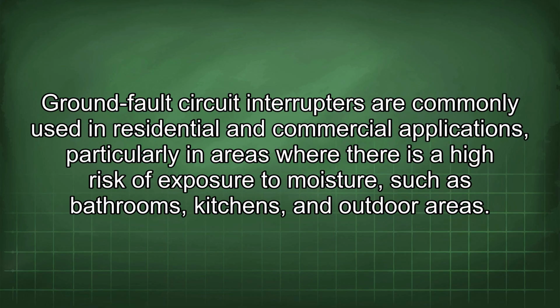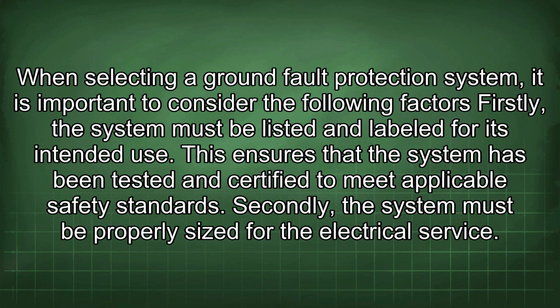Ground fault circuit interrupters are commonly used in residential and commercial applications, particularly in areas where there is a high risk of exposure to moisture, such as bathrooms, kitchens, and outdoor areas. When selecting a ground fault protection system, it is important to consider the following factors. Firstly, the system must be listed and labeled for its intended use. This ensures that the system has been tested and certified to meet applicable safety standards.